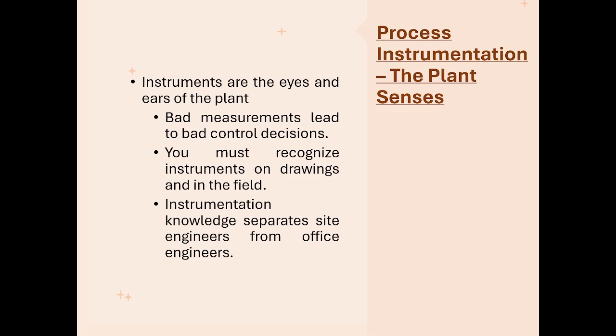Okay, so moving further, talking about process instrumentation, which is the plant senses, we use instruments, and instruments are the eyes and ears of the plant. They tell the control system what is happening in the real world. So if an instrument gives wrong information, the PLC will act, but it will act wrongly. So a site-ready engineer can recognize instruments both on drawings and physically in the field. Now this knowledge separates engineers who can solve problems from those who only escalate the problems. So let's briefly look at the main process variables every plant depends on.